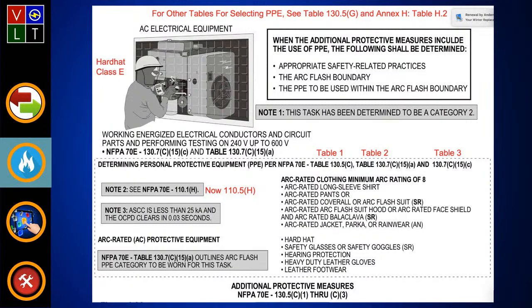Now, notice that's what took place here. This guy here, he's working on energized conductors and circuit parts, performing testing on 240 volt up to 600 volt. So I go to my table 130.5C, and it says for that task, I need equipment. So I go to table 2, I look at 130.7C15A, and for that task, I need a category 2. Okay, gotcha. So that makes sense. And now I go over and I look at the one thing I'll point out, 110.1H is now 110.5H, and that's labeling. We'll look at that.